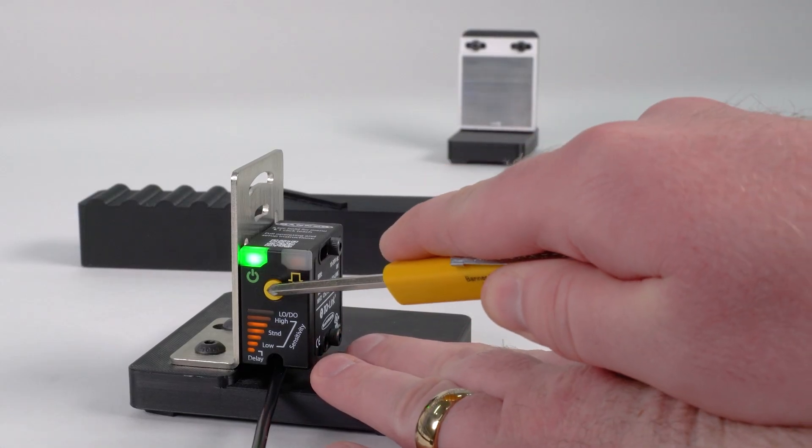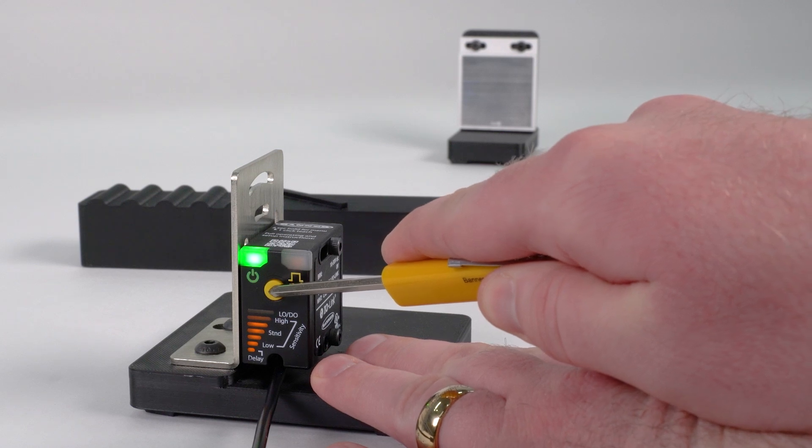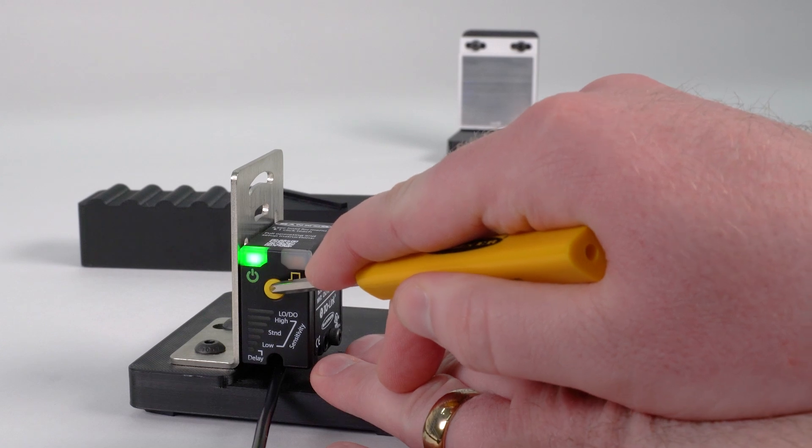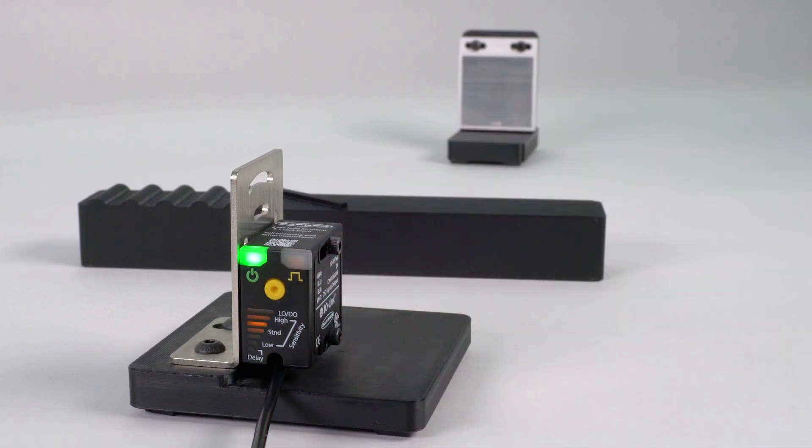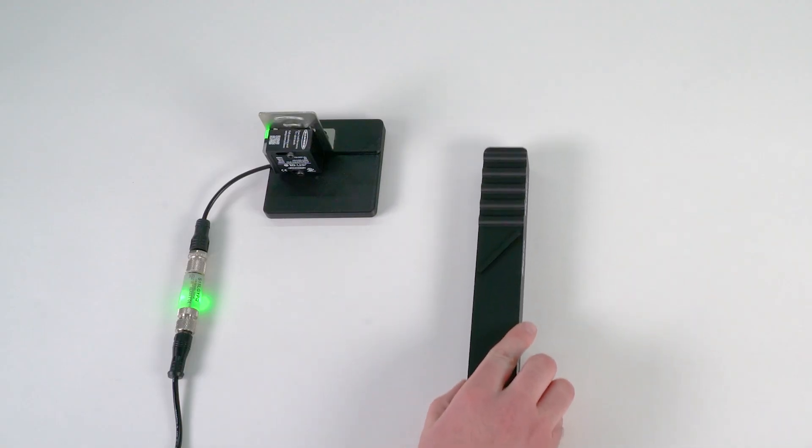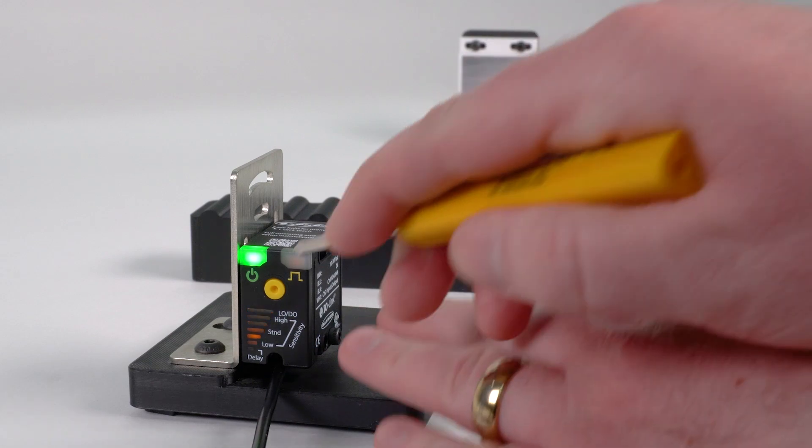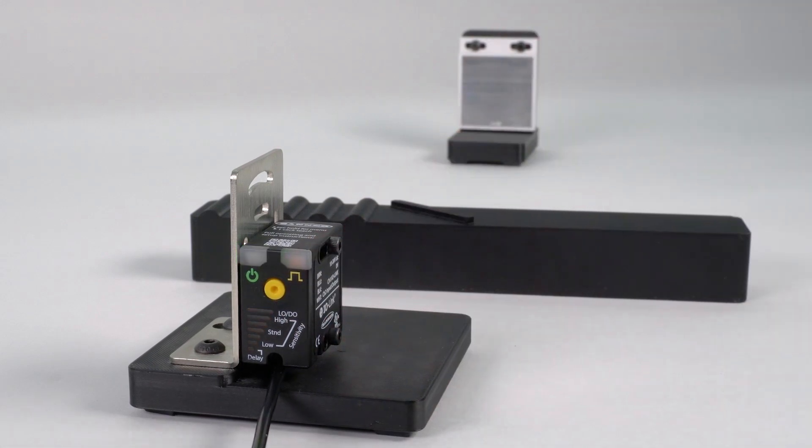To perform a dynamic teach, begin by putting the sensor into configuration mode and then press the button two times. The bar graph LEDs will begin cycling up and down to indicate that the teach process has begun. Present multiple obstruction conditions and then press the teach button one more time. The green and amber LEDs will flash twice to confirm that the teach was successful.